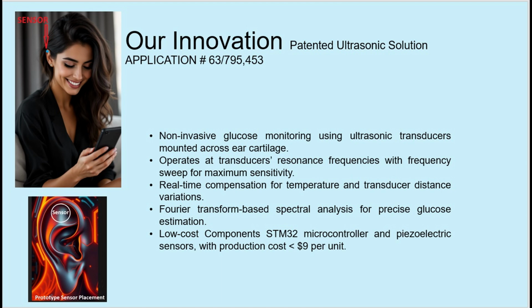These transducers operate at their natural resonance frequencies, ensuring maximum signal sensitivity. Additionally, a frequency sweep near the resonance points allows us to perform spectral analysis with high resolution. We incorporate real-time compensation for both temperature fluctuations and mechanical pressure, including changes in the distance between transducers. These variables can significantly impact ultrasonic signal behavior, but our system accounts for them dynamically to maintain accuracy. To interpret the signals, we apply Fourier transform-based spectral analysis, extracting precise information from the ultrasonic waveforms that correlates with glucose concentration in the interstitial fluid.